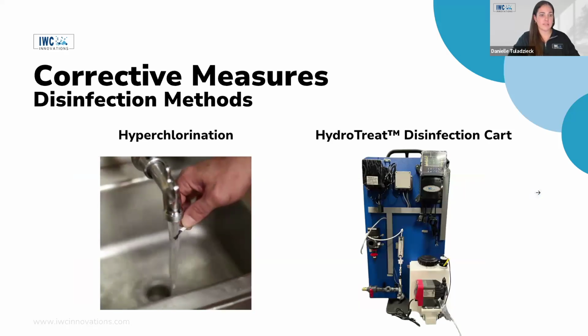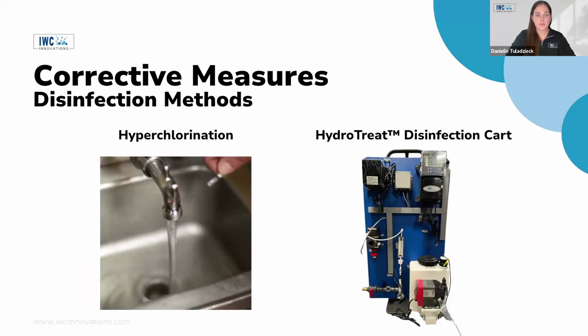Now let's address those root causes. We have to understand what elements of the system contributed to the colonization. Then, as those things are being addressed, the system needs to be reset to a clean starting point. The chemical shock treatment, or hyperchlorination, is effective as an immediate correction, especially during case investigation and response. When we have a lower risk situation but still have a system that requires cleanup, our HydroTreat temporary disinfection cart is a great solution with no system downtime. As Legionella growth management is a journey, some systems at the end of the process will require permanent installation of supplemental disinfection. IWC can walk through this process with you to ensure the correct approach for your mitigation efforts.